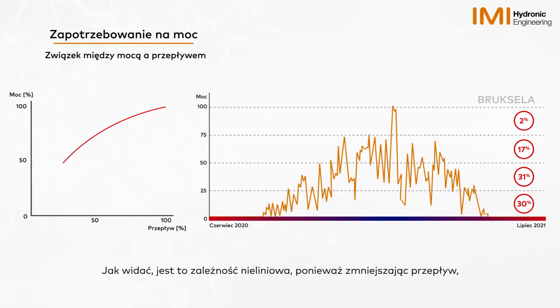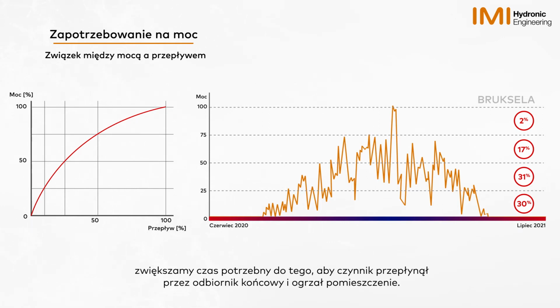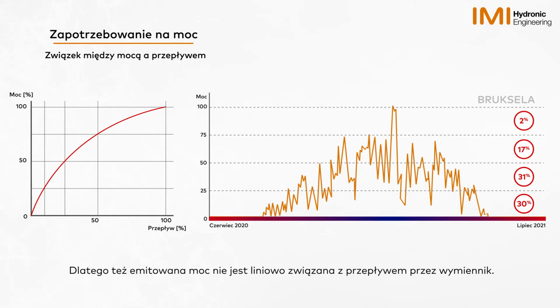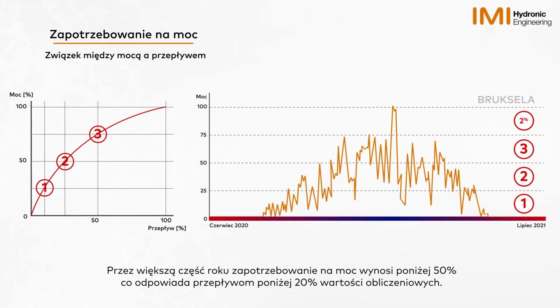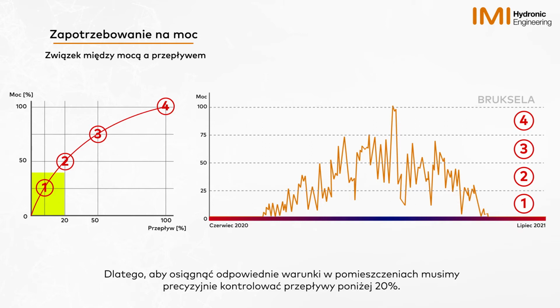As you can see, this is a non-linear relationship because as we reduce flow, we increase the time taken for the fluid to pass through the terminal unit and heat the surroundings. Therefore, the power emitted is not linearly related to the flow going through the unit. For most of the year, the power demand is below 50%, working with flows below 20%. Therefore, to achieve energy efficient indoor climates, we need to accurately control flows below 20%.